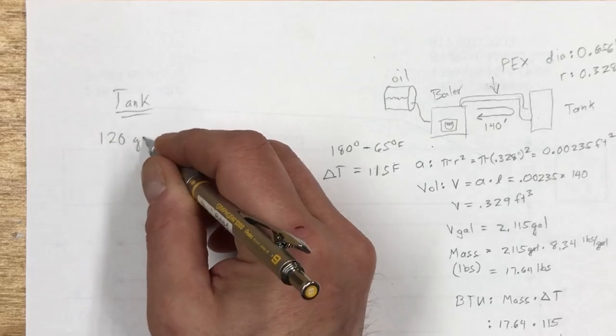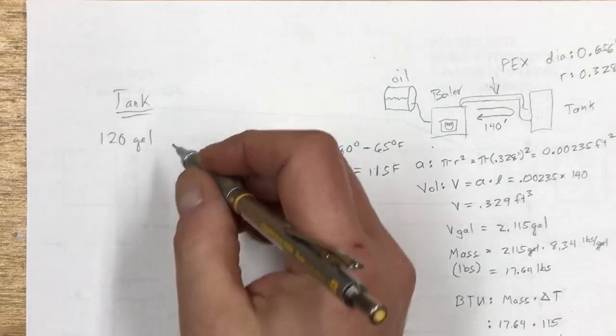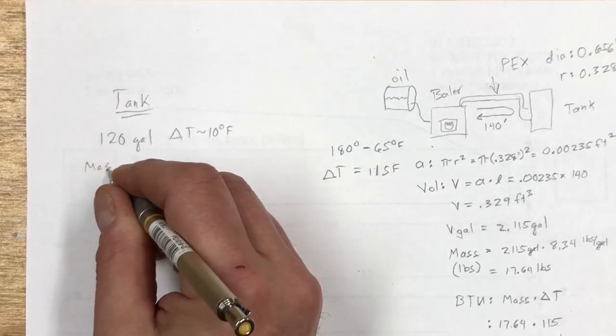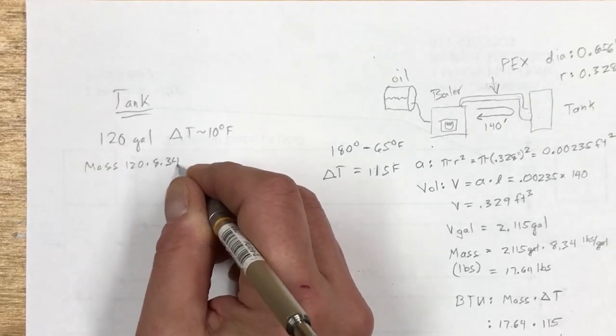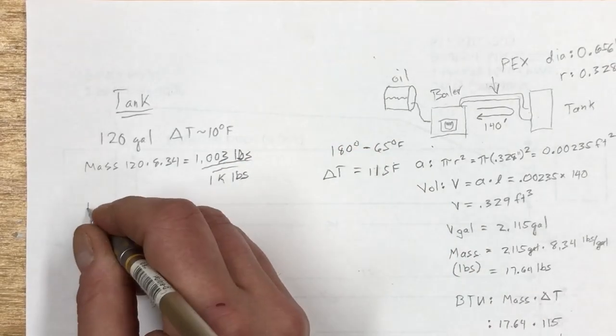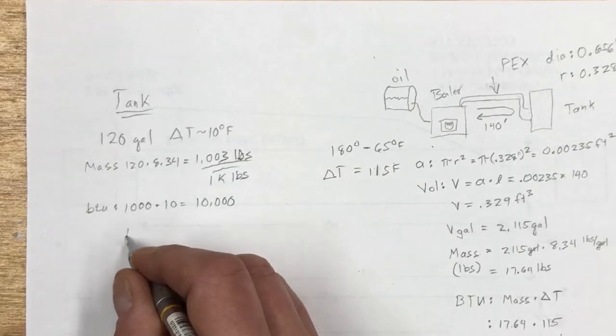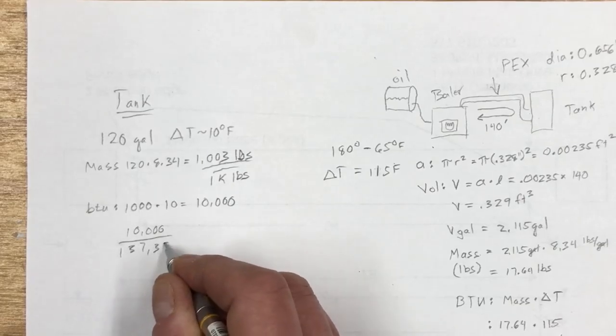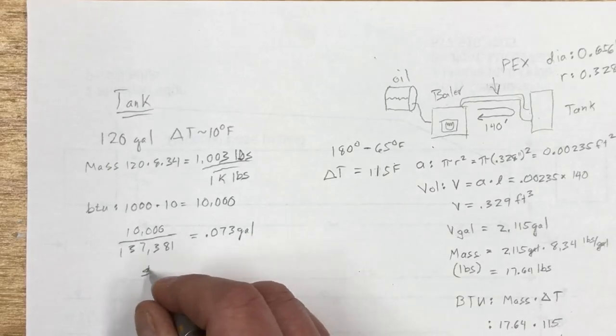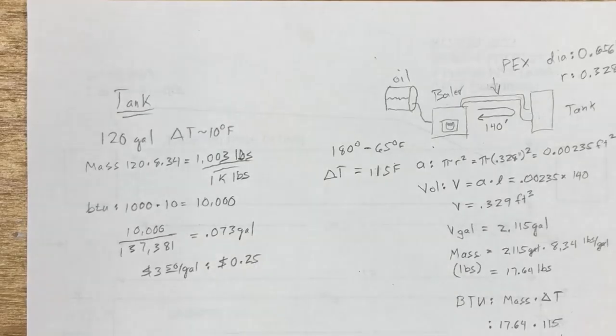So over here let's talk about the tank. It's 120 gallons and from what I understand the boiler will turn on and top it off for a delta T of about 10 degrees, again this is all fahrenheit. So the mass of the water in the tank is 120 times 8.34 which equals one thousand and three pounds and I'm going to round that up to thousand pounds. So the BTU would be a thousand times delta T of 10 is obviously ten thousand. And if you divide ten thousand into one hundred and thirty seven thousand three hundred and eighty one BTU in a gallon you end up with 0.073 gallons. And again at three dollars and fifty cents per gallon that turns out to be zero point two five dollars or 25 cents.